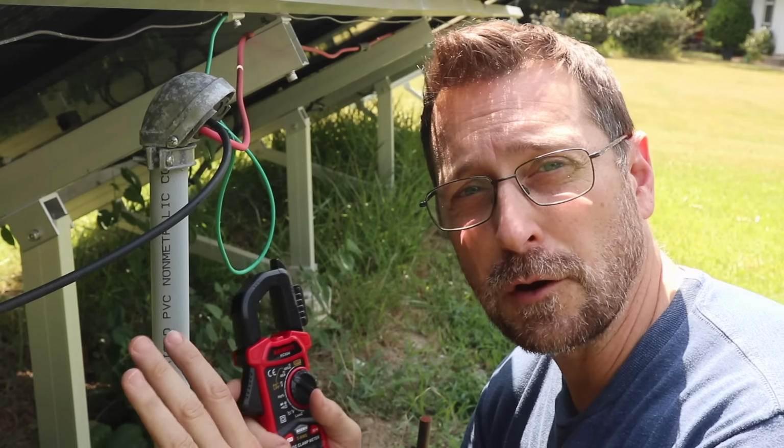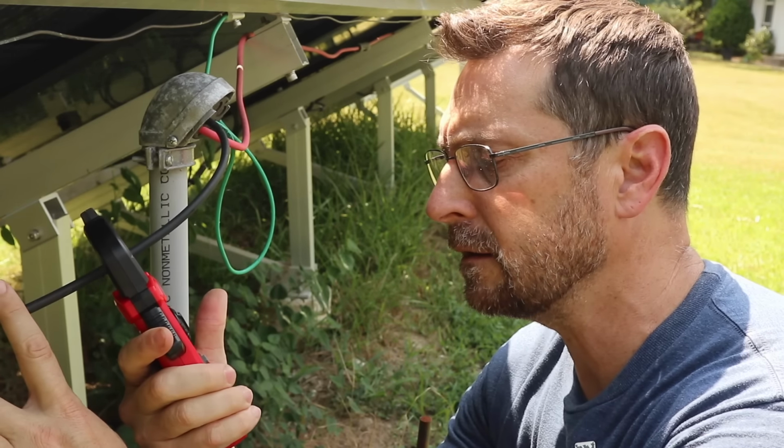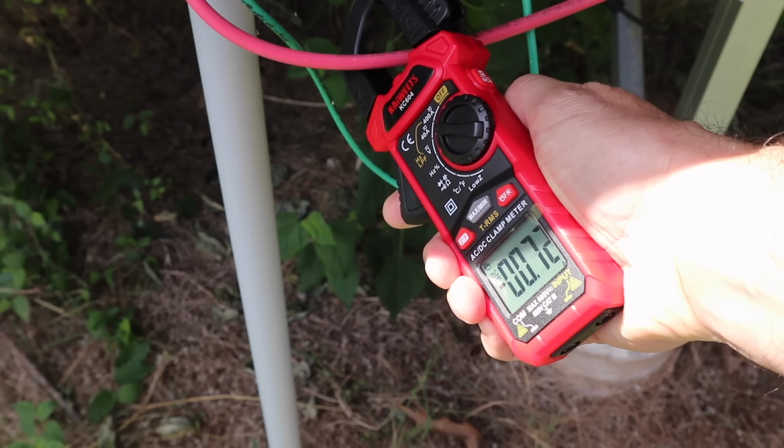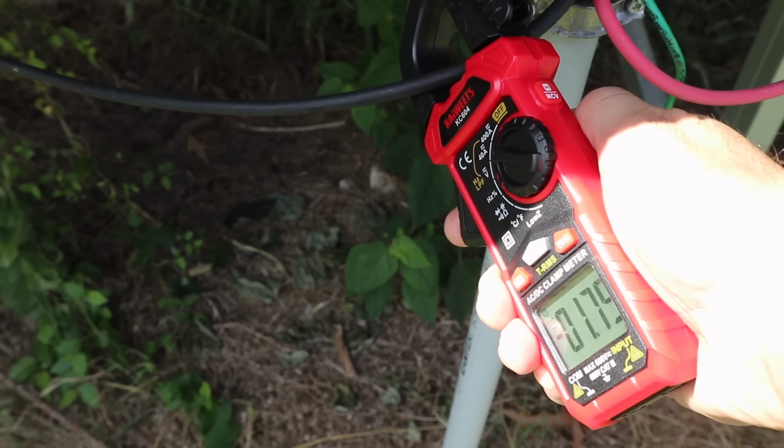So here we are at our front array, which I suspect is the problem child, and we're going to look at it. So you can see it's certainly an amperage problem. Our amps are jumping all over the place. And you can see that's the case on the negative also. So if you have a current problem or amperage problem and not a voltage problem, this is what it could be. So what it means is we either have high resistance somewhere or low resistance on another path.